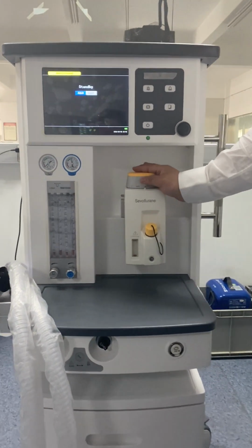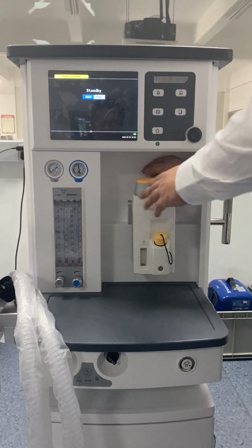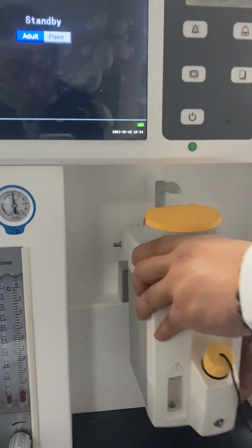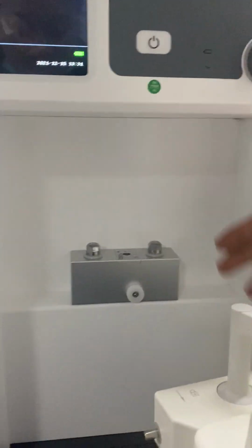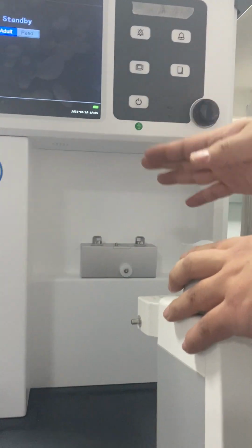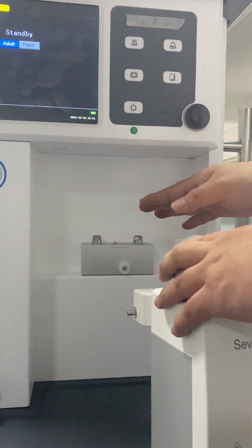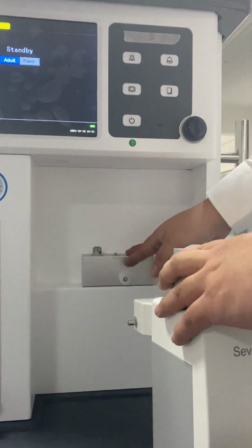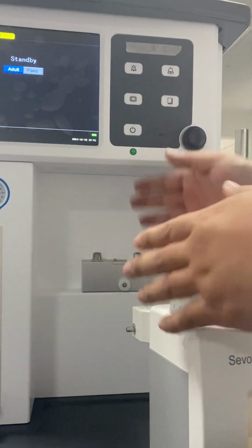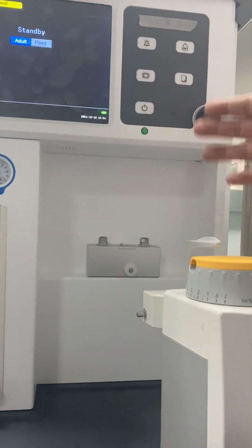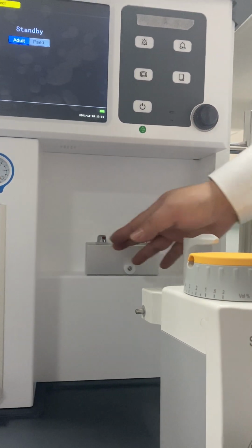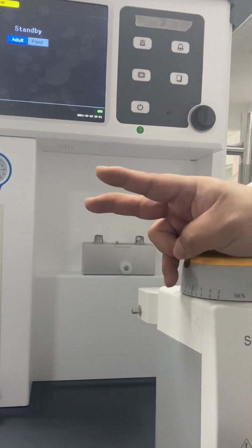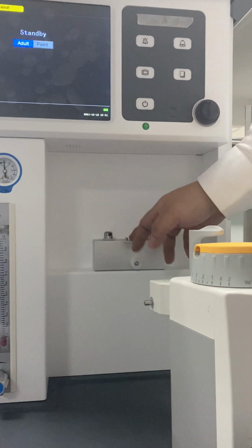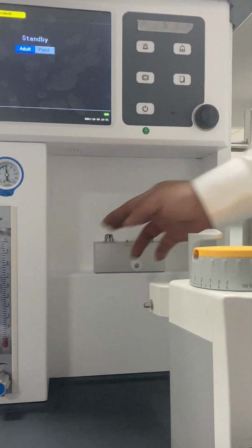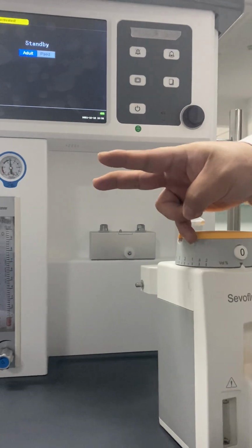And here this position is for the vaporizer. As you can see here, for the anesthesia machine, if you are only equipped with one vaporizer, then before the shipment in our factory, we can put this foundation on the middle side, so it can keep the machine looking very steady and beautiful. But actually this machine can take 2 vaporizer positions together. So if you are equipped with 2 vaporizers, then it will not be in the middle. It will be one on the left side and one on the right side. So it can take 2 vaporizers at most.